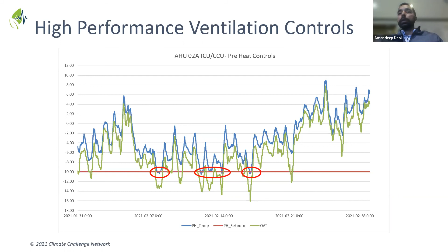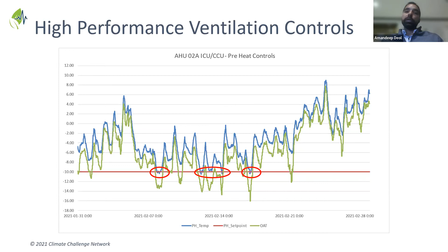And I think you told me, Amandeep, that in many of the hospitals you look at, that preheat temperature is set at plus 3 or 4 or 5 degrees. Yes, that is true, and that's what we're currently doing, working with other hospitals in the greening healthcare research. A lot of the hospitals have set those preheat temperatures too high, and there's no clear direction to hospitals on what the right set point should be. In this case, we can see a perfect example that within Ontario, this preheat set point is working well for this hospital.